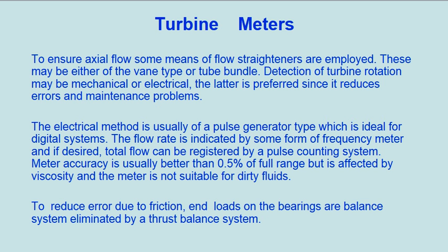The electrical method is usually of a pulse generator type, which is ideal for digital systems. The flow rate is indicated by some form of frequency meter and, if desired, total flow can be registered by a pulse counting system. Meter accuracy is usually better than 0.5% of full range, but is affected by viscosity, and the meter is not suitable for dirty fluids.